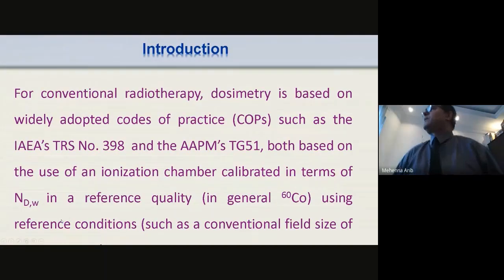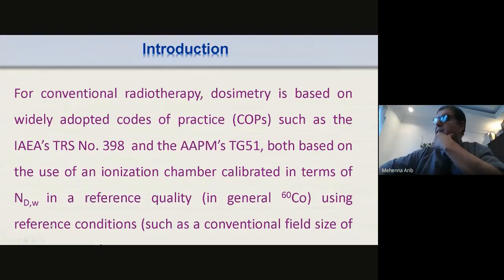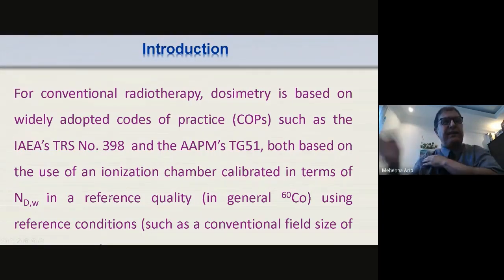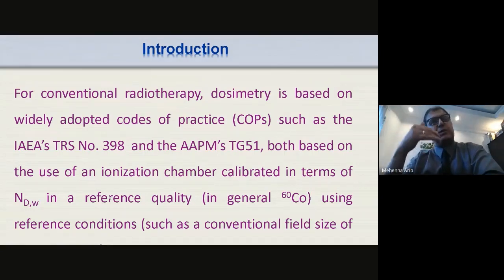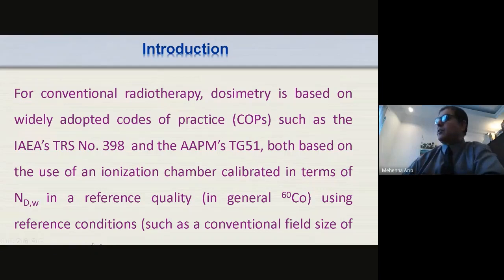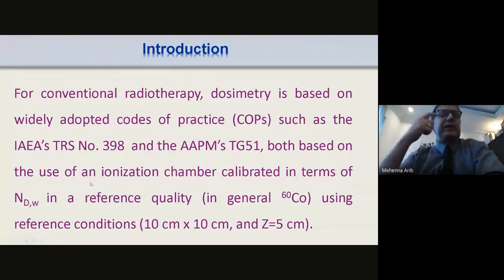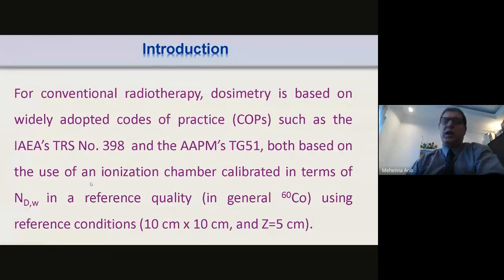So when it comes to the dosimetry of radiotherapy beams, everybody knows the well-known code of practice TRS 398, which gives the absorbed dose to water, starting from one ionization chamber calibrated in terms of absorbed dose. This chamber is usually calibrated in cobalt-60, and then you apply an energy dependence calibration factor, kQ,Q0, to calculate the corresponding calibration coefficient for the high energy photon or electron beams. The calibration is actually performed in reference conditions, particularly with a 10 by 10 field size.